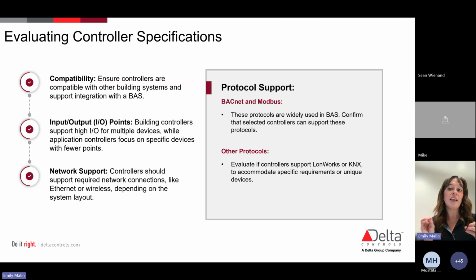You really have to start thinking about, like Moose had that diagram of all of our network infrastructure, how these are going to be talking to each one of our different components. So if you're using an Ethernet network, you're going to want to choose a controller that supports onboard Ethernet, right? Or have a plan to get that controller talking on an Ethernet protocol. Again, we talked a lot about BACnet. We talked a lot about BACnet Secure Connect. If you want that extra security, make sure you're choosing a controller that supports that.